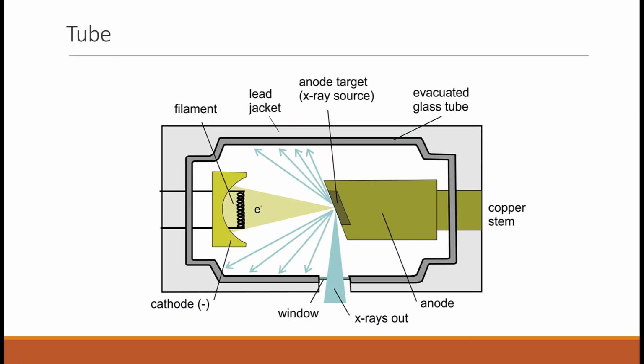Let's talk a little bit about the source of the X-rays, the X-ray tube. As I said, it's kind of a glorified light bulb. What we're doing is applying an incredible amount of voltage to it, about 30 kilovolts, in order to drive this system. We do that to a cathode on one side. It runs through a filament wire that generates a boatload of electrons that are propagated towards an anode down at the other end. The electrons then hit the anode.